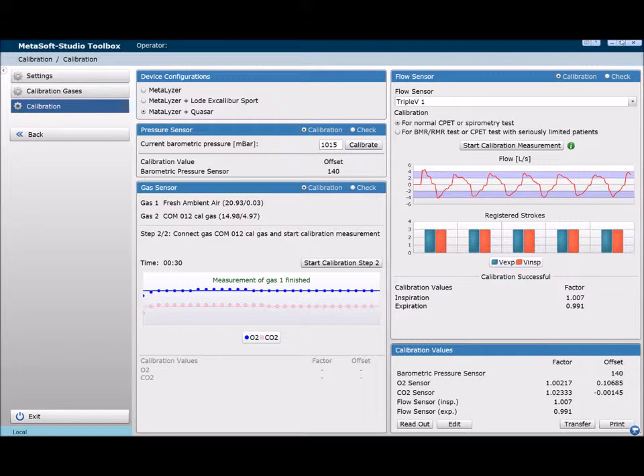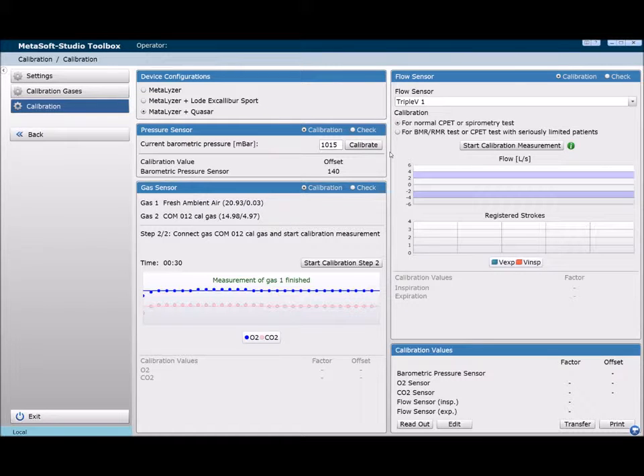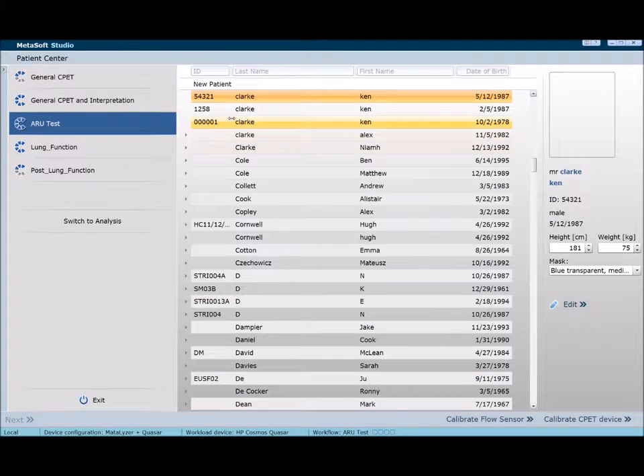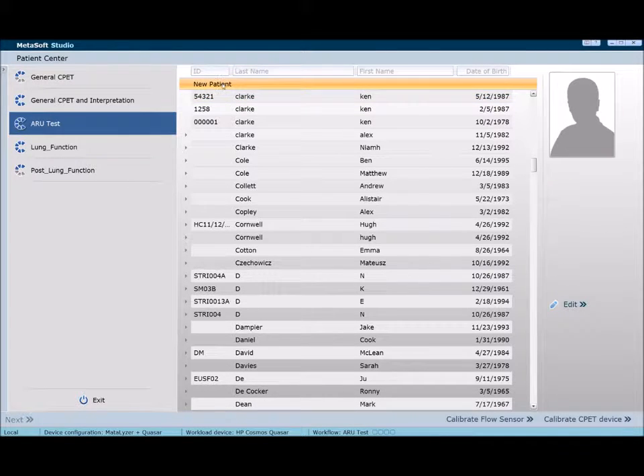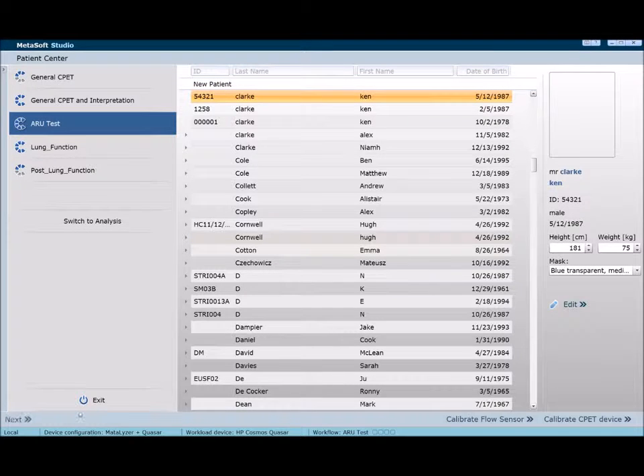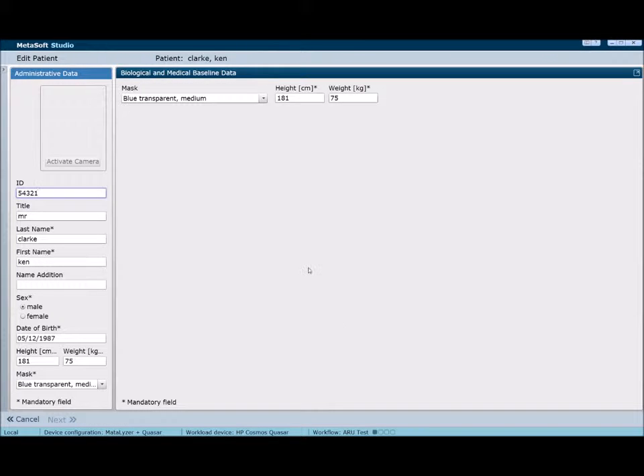open Metasoft Studio and click ARU Test. Then click on New Patient or scroll to an existing patient followed by clicking Next. Enter the patient's details and ensure to update their height and weight for every test. Then click Next to choose or create your protocol. Once the protocol has been chosen, click Sensor Adjustment, which takes approximately a minute to complete.